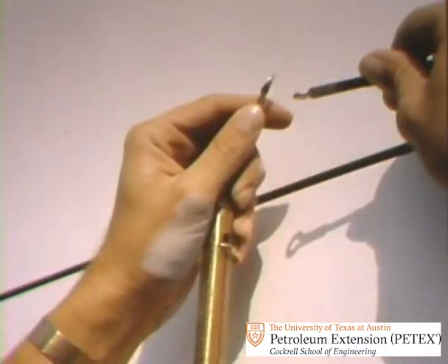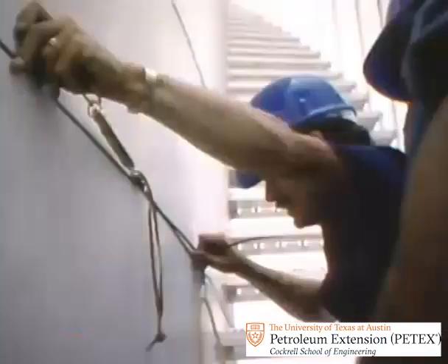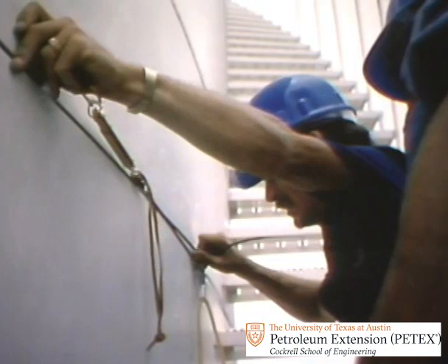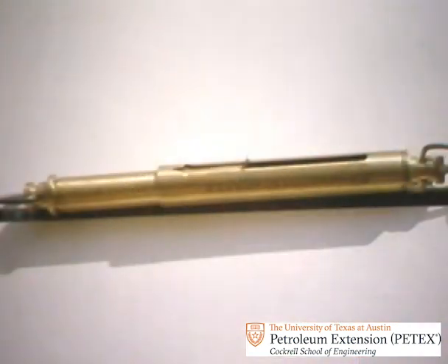After breaking surface tension, a crewman attaches the clamp and tension gauge. Then, enough tension is applied on the working tape until its reading is the same as taken by the standard tape. They read and record the amount of tension applied to get the working tape to give the same circumference measurement as that obtained with the standard tape. This tension reading may be different from the tension required on the standard tape. In this case, it's 22 pounds versus 10 for the standard tape.